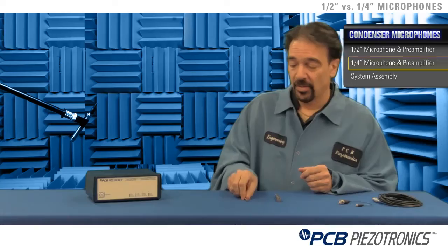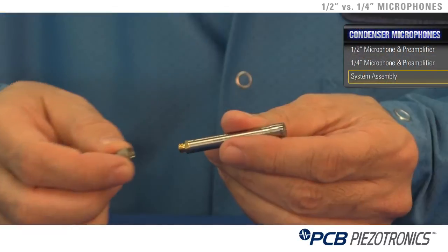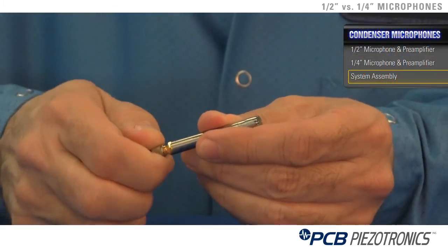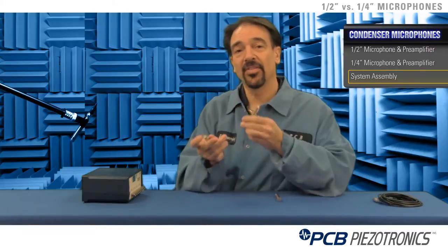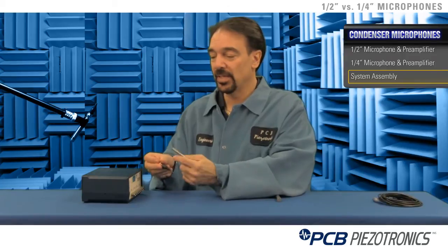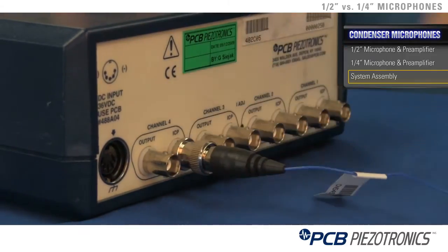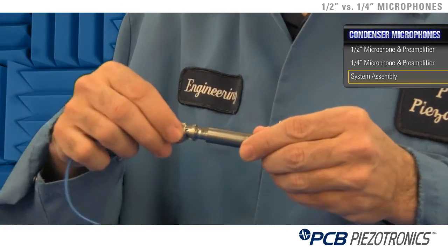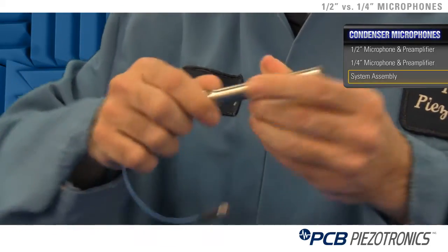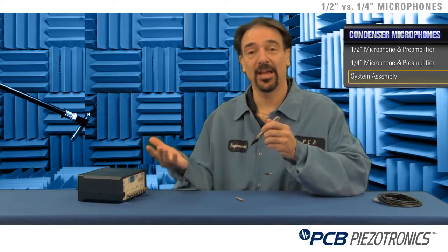The way the system gets put together, the pre-polarized design will take a 10-32 micro dot connector that screws into the preamp, and then your BNC connector on the other end typically will go into your signal conditioner or your data acquisition system. Your half inch microphone terminates in a BNC connector, so you would have a BNC to BNC connector here, and your end terminating cable will be BNC also to go to your signal conditioner or data acquisition system.